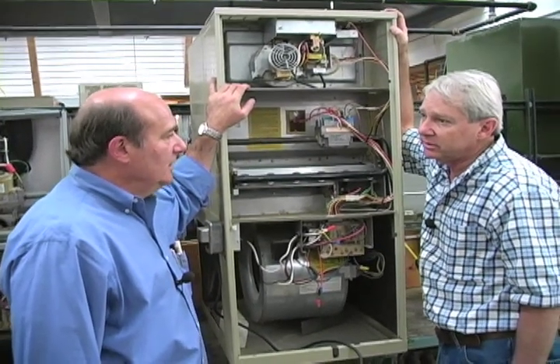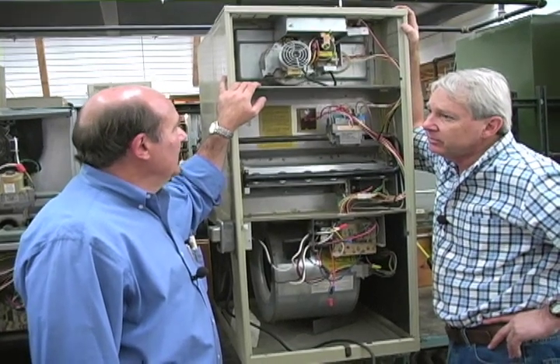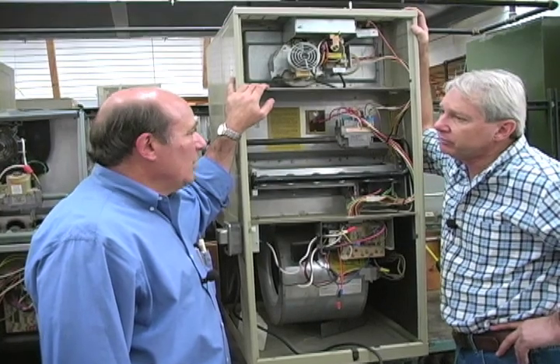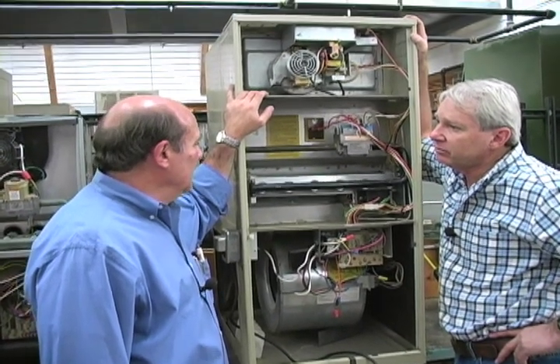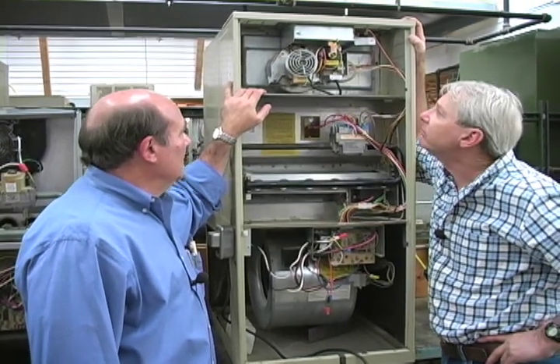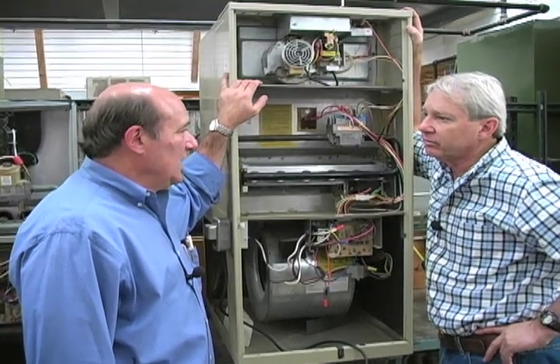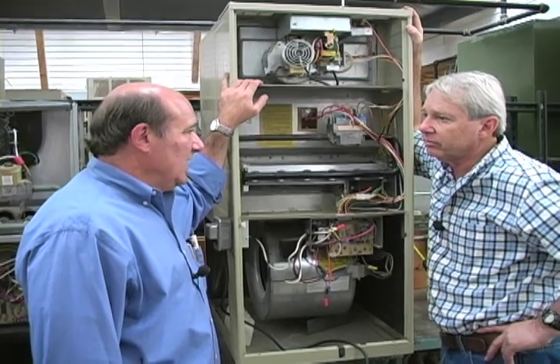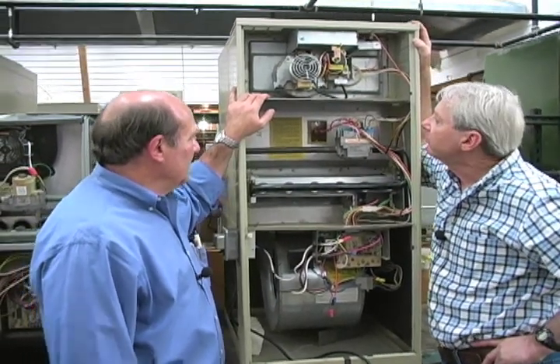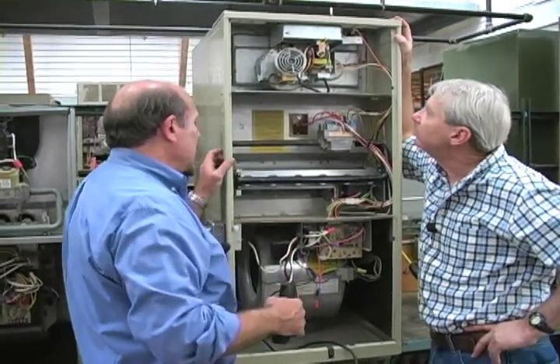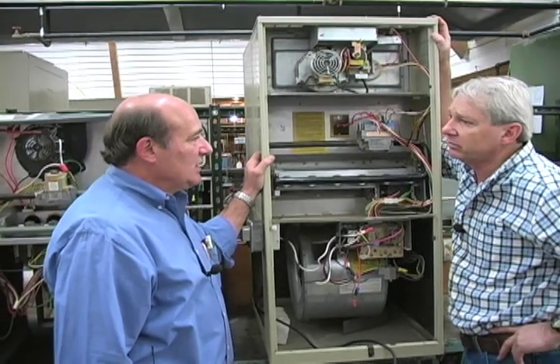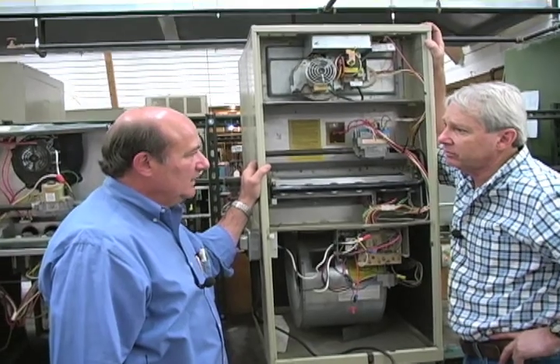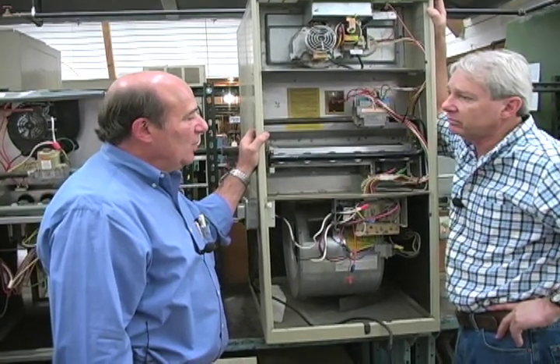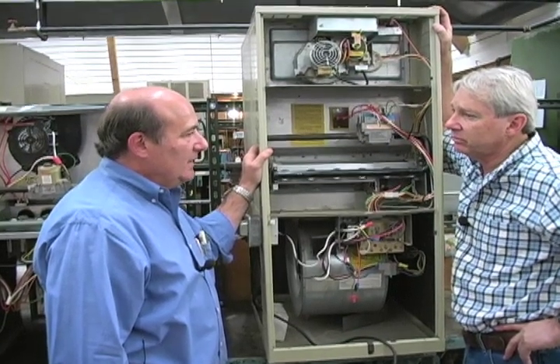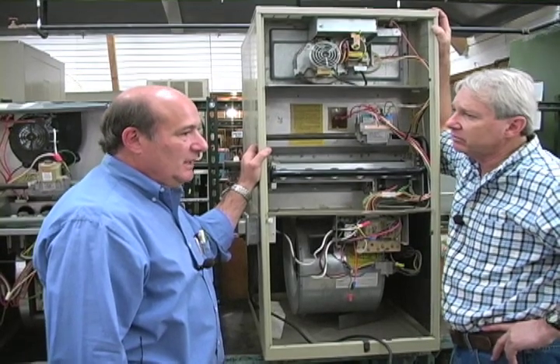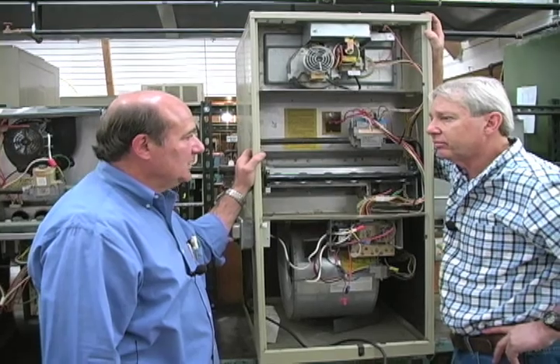Yeah, well, no doubt it was heated from the exhaust gas. But what they do on these things, Kent, is that these combustion blower motors have varying capacities based upon how big the furnace is, how much gas is coming through them, and the manufacturer of the combustion blower motor might have one or two size blowers, but you may have one furnace that's a 60,000 BTU, another that's 120,000 BTU, and you can see that the bigger the burner compartment, the more area you need to bring through it. Right. So that combustion blower motor may have been sized for the biggest furnace, but then when they put it in a smaller one, they partially restrict the opening on that combustion blower so that we don't develop overpressurization of that exhaust flue. Don't forget, in many of these cases, that exhaust flue, the chimney, is going up through the roof. It might have a water heater or some other appliance piped into it as well.